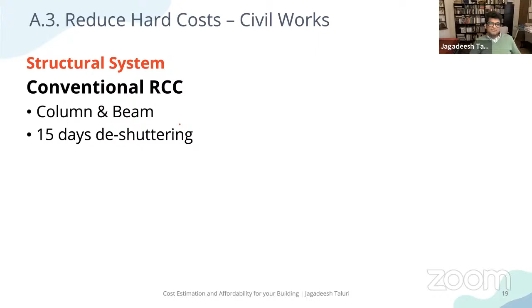In the same way, you can also leverage the structural system to right size your building. For example, if you take a conventional RCC column-beam structural system, a typical office building grid will be, let's say, 10 meters. If you want to span 10 meters between columns, your beam depth will be almost 1 meter or 0.6 meter depending on what you're doing. So you have the beams, then false ceiling for the ducts, then the floor, so typical floor-to-floor height ends up being around 4.2 meters.